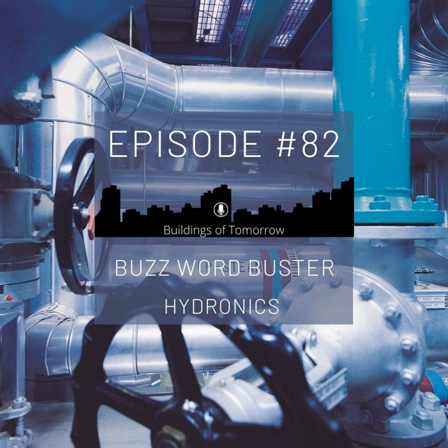So that's why we, and also the pump manufacturers, say, rather than maintaining a constant pump head, why don't we lower the provided pump head continuously, most of the time to a point where at very low flow, we reach about half of what we had as a pump head at design. And that is then often called delta P proportional.